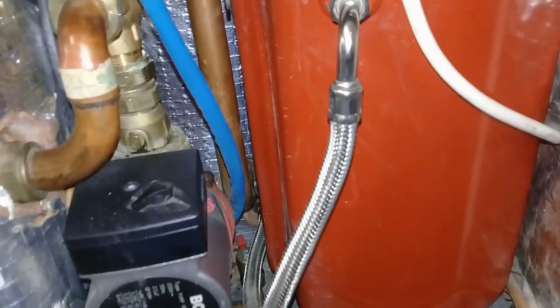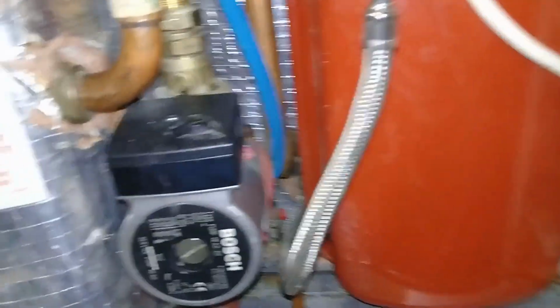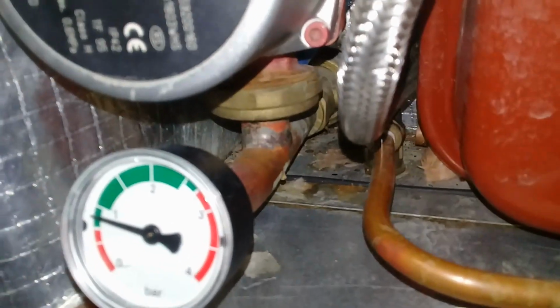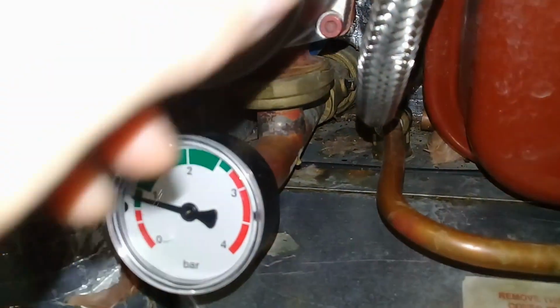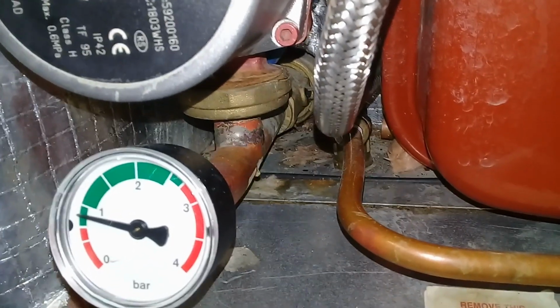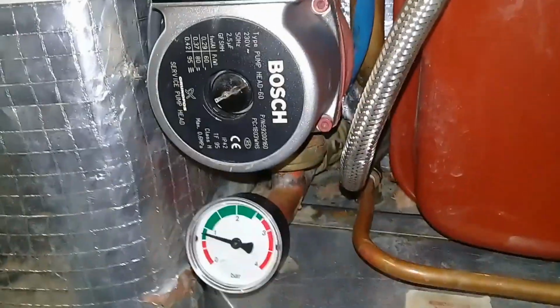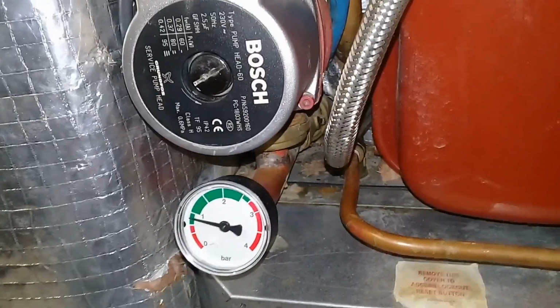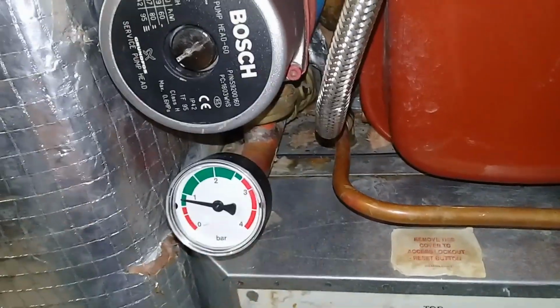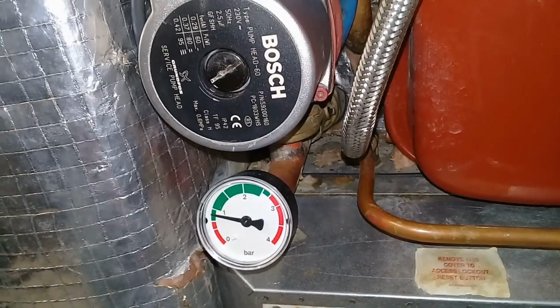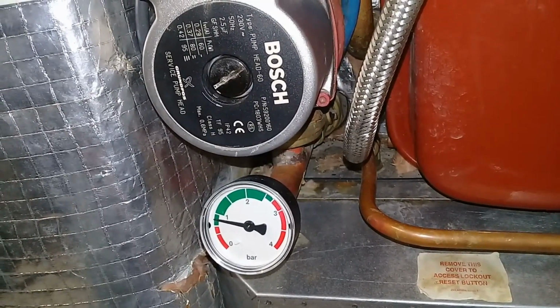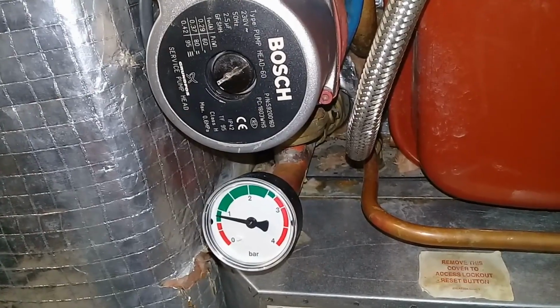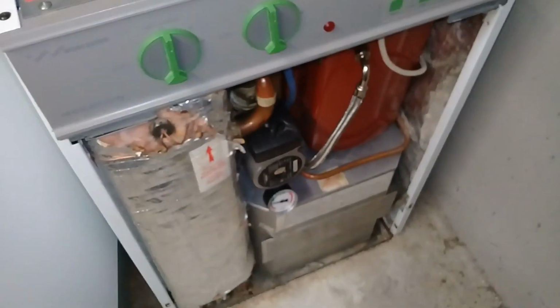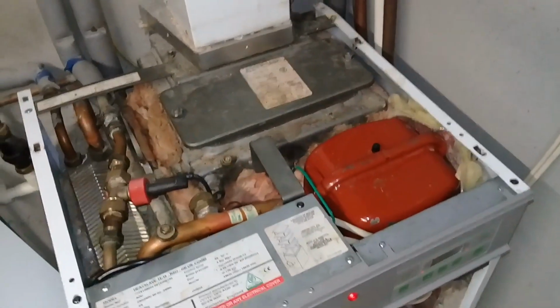Interestingly enough, when I emptied this old one of water, put it all back together and connected it, there was a slight weep coming out of the pump valve, which to me indicated the flow was back again and the pressure. The boiler just seemed to work a lot better until this thing started filling up with water again. But it was totally different behaviour from water being forced out under pressure and this pressure gauge going up. It just wasn't behaving like that at all. So you get slightly different behaviour on these Heatslave boilers. I hope it does help someone, because you could end up spending a lot of time replacing parts that don't need to be replaced.